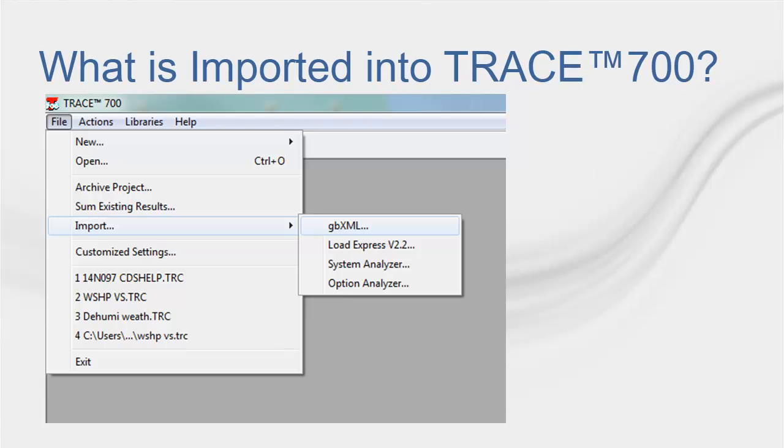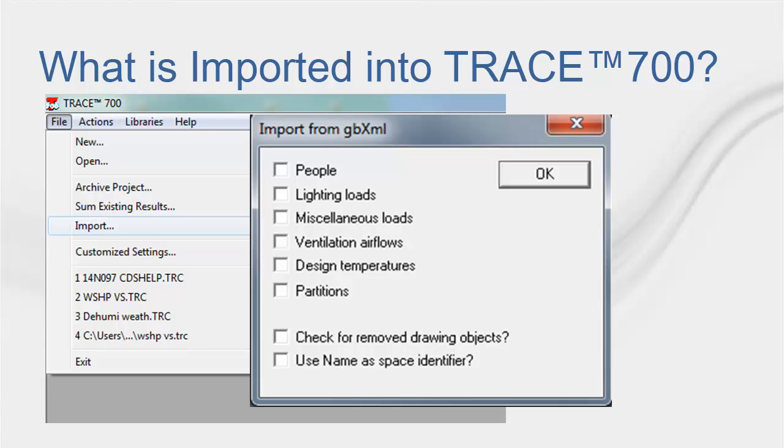When importing a GBXML file into Trace 700, a selection must be made of what wants to be imported. Depending on the attributes of the CAD model, Trace can import, if available, internal loads like people, lighting, and miscellaneous loads, ventilation loads, design temperatures, and partitions. Remember that partitions in Trace 700 are internal walls meant to separate areas that have a big temperature difference. If your interior walls separate areas with similar temperatures, you don't need to import them.